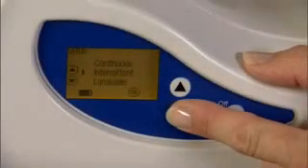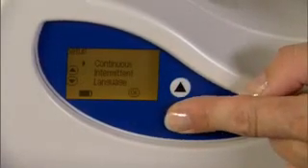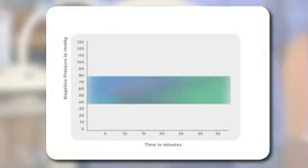The state-of-the-art technology and engineering of the Pro Series features the most highly refined and customizable intermittent therapy options available, putting control in the hands of the clinicians and allowing NPWT to extend to its ultimate potential. We call the result variable pressure therapy. Prospera is designed for VPT. You can see here that our recommended pressure ranges are between minus 40 and minus 80 millimeters of mercury.